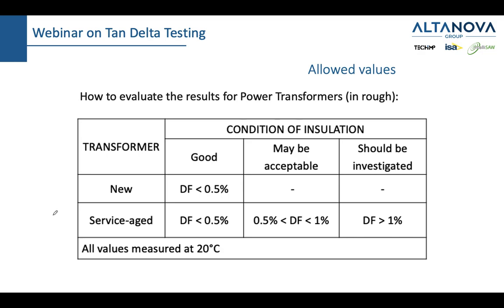And let me give you some numbers now. How do we know that the result is good? How do we know that we measured a good value for tan delta? Well, I would say that this, what you see right here, which we will discuss right now, is also standard, but it is not the only standard. So this is an IEEE standard, and for a new transformer in general, the tan delta or dissipation factor should be less than 0.5. Then, if the number is between 0.5 and 1 for a service-aged transformer, then we talk about also good insulation, acceptable insulation, and only if tan delta is bigger than 1%, only in that case we have the right to suspect that there are some problems happening inside.